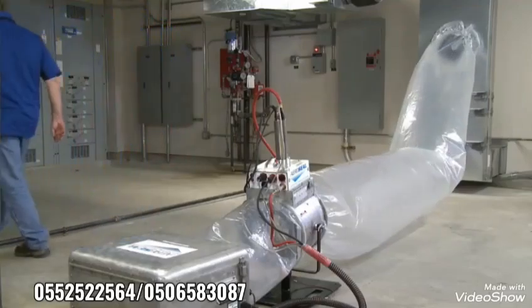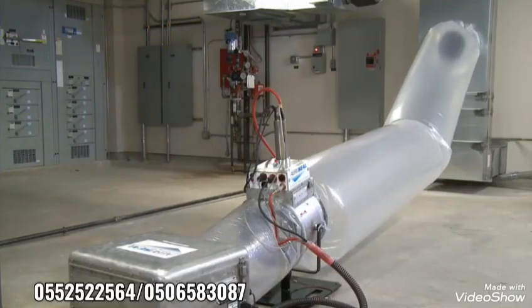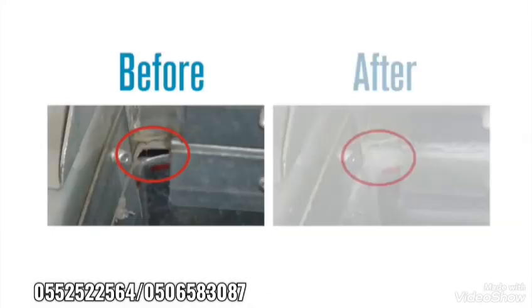The patented computer-controlled injection machine begins to heat up adhesive particles suspended in liquid. As the particles are heated, they dry up and become suspended in air. The AeroSeal technology uses a fan to blow these small dry adhesive particles into the blocked duct system at a constant rate of speed. As the particles approach a small hole and try to escape the ductwork, they stick to the side of the hole. As more and more particles repeat the same action, the hole is soon filled. The AeroSeal process does not coat the interior of the ductwork and can seal holes as big as 5/8 of an inch.